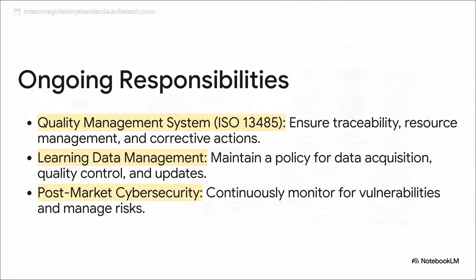All of this ongoing work is managed under something called a quality management system, or a QMS. This system, which really should follow the medical device standard ISO 13485, is the rulebook for everything you do, from how you manage your training data to how you handle customer complaints. In your cybersecurity work, it never, ever stops. You have to have a post-market plan to constantly watch for new threats, figure out the risk, and manage any vulnerabilities for the entire life of the device.